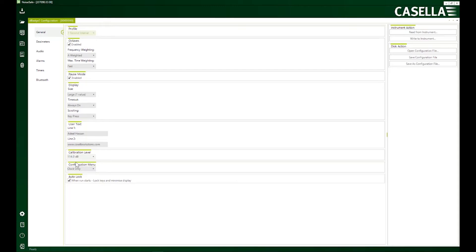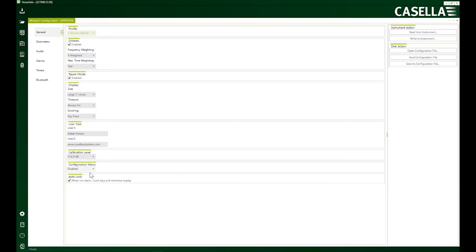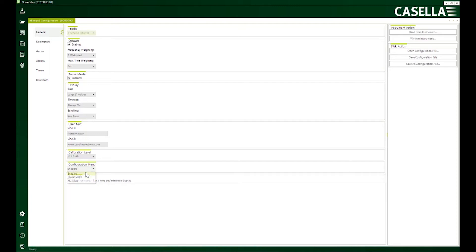This configuration menu is basically a security settings to avoid any sort of tampering. So if I disable it, then the user of the device will not be able to access the configuration menu available on the device. If I set it to clock only, they would only have access to clock. And if I enable it, of course, they will have complete access to the configuration menu.